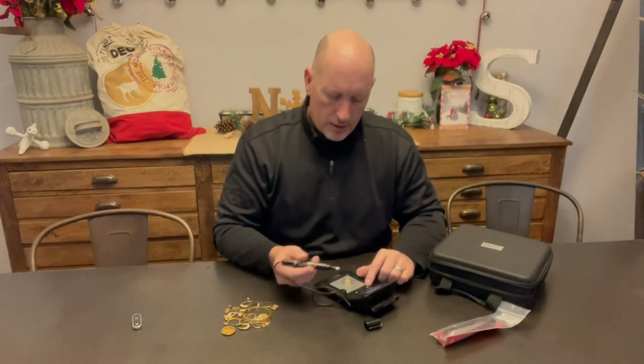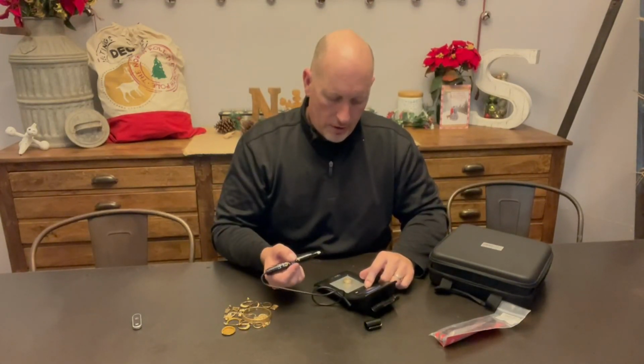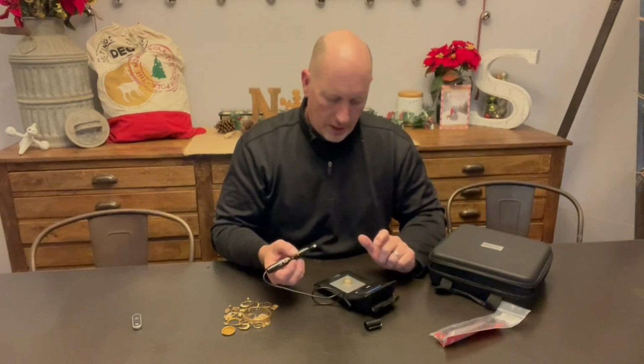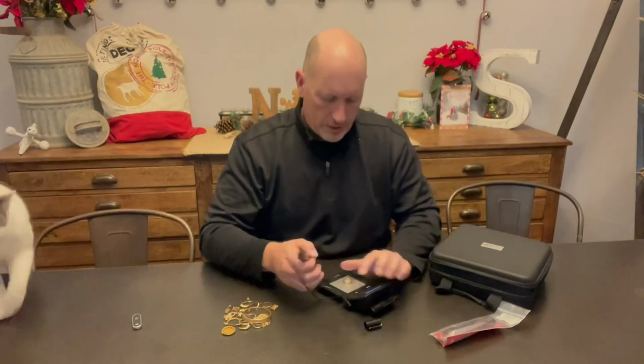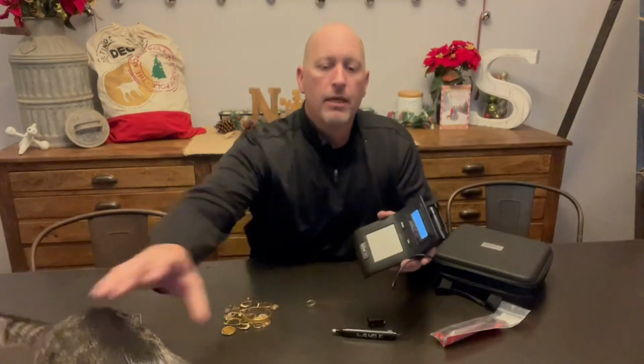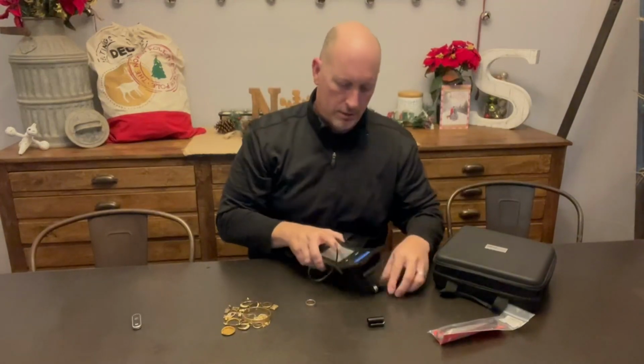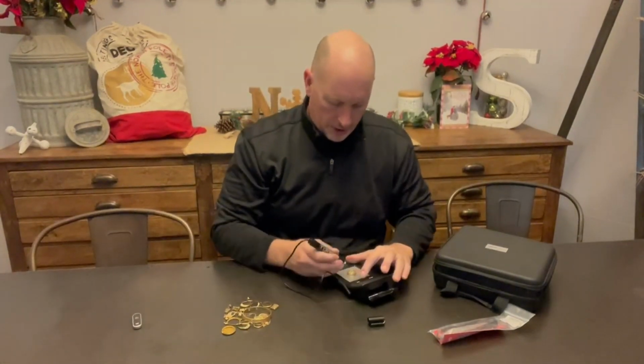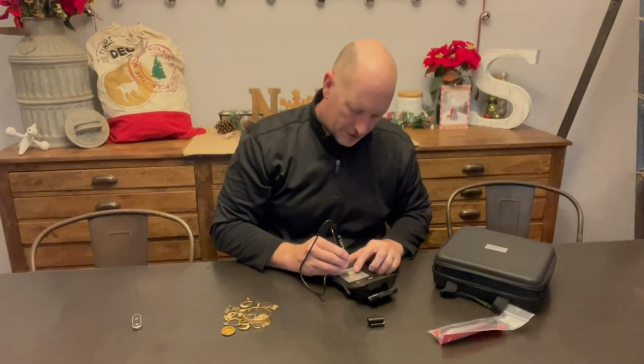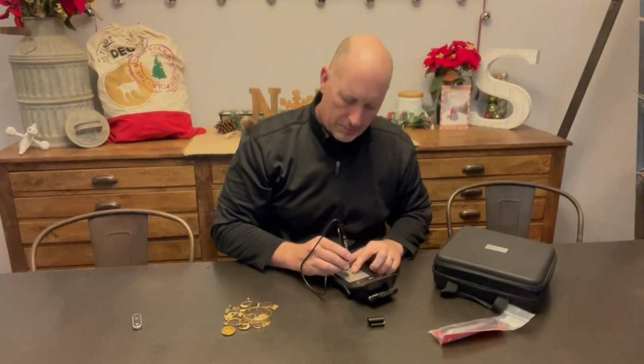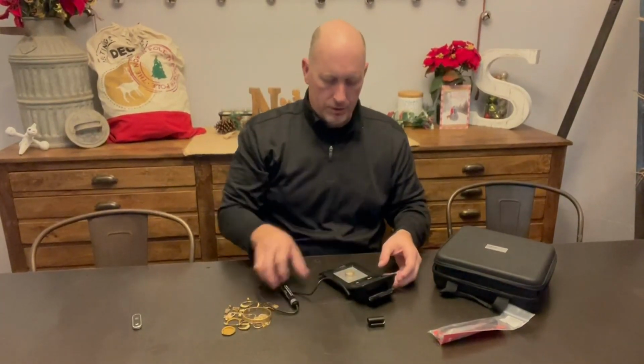I'm in quick test mode right now. Oops. And then I just click it once. Oh, I'm sorry. There's a calibration button right here. You just push the calibration button. Get this ready to go. Push your calibration button. And then it gives you a few seconds. You get your test piece on here, and it'll go through a calibration mode right here. And in a few seconds, boom, and then now, oops, well, it's over. It says success when you've successfully calibrated the machine. Now my machine's ready to go.